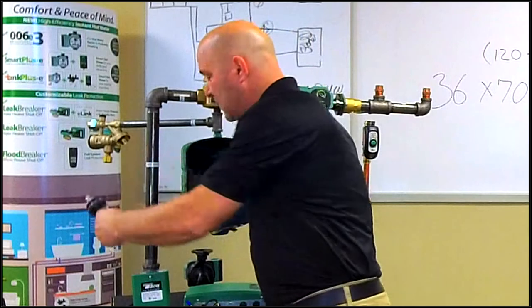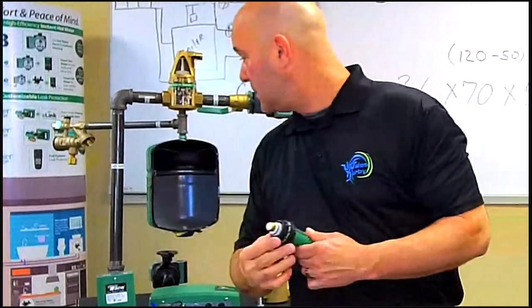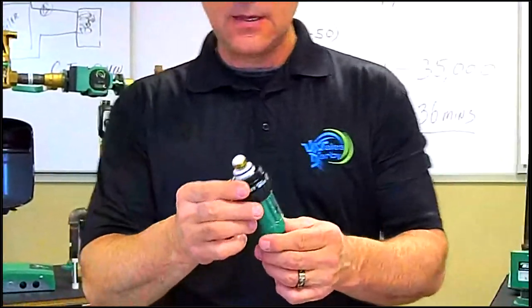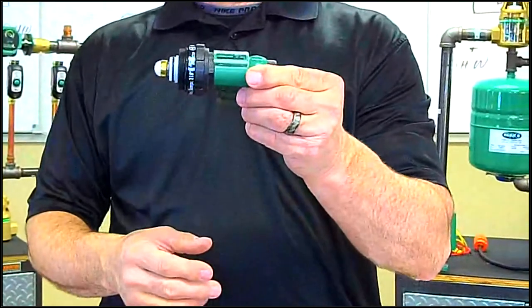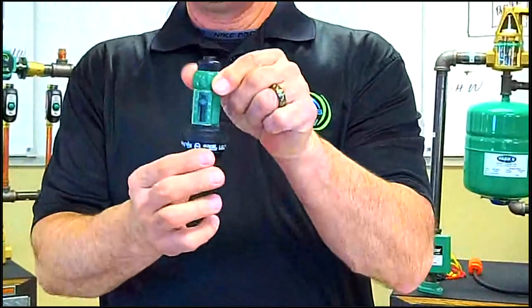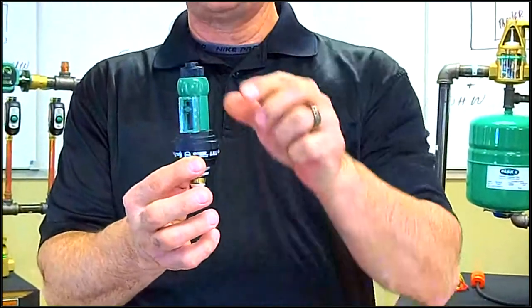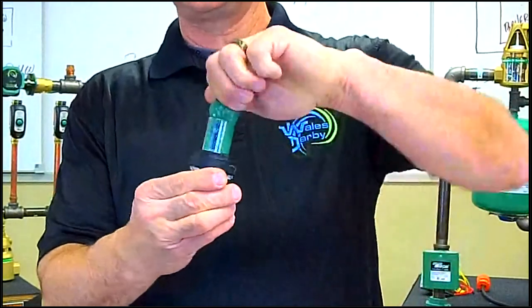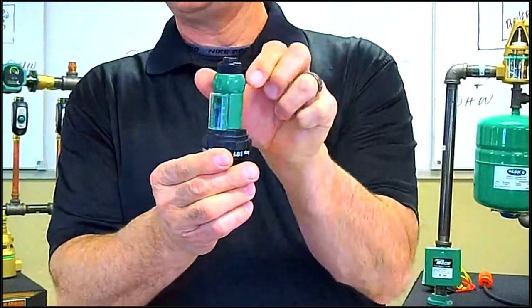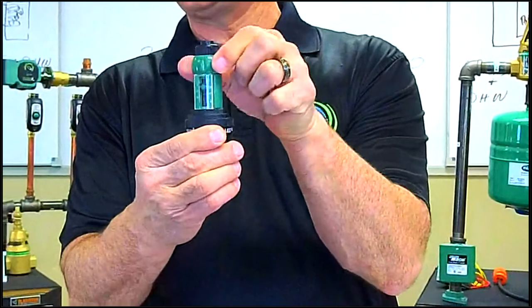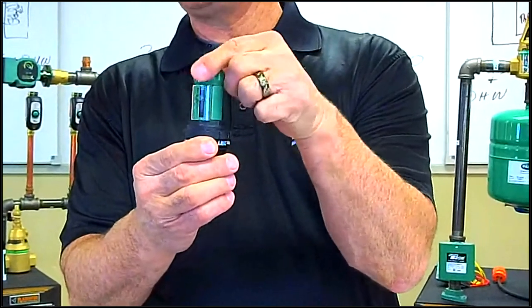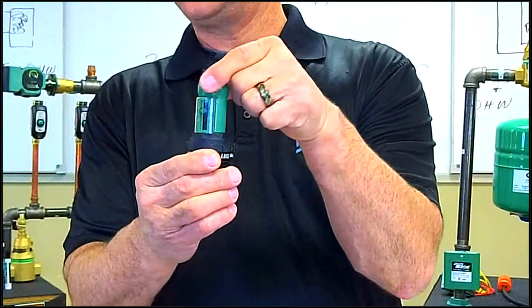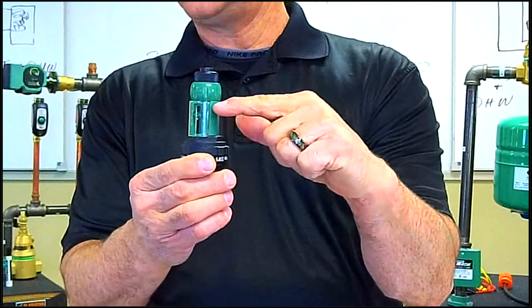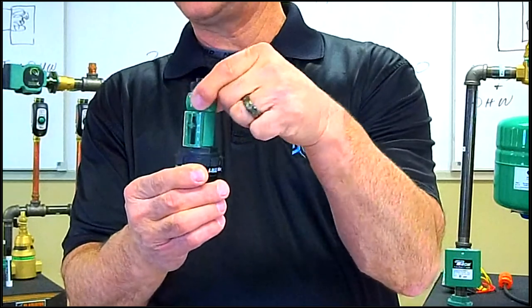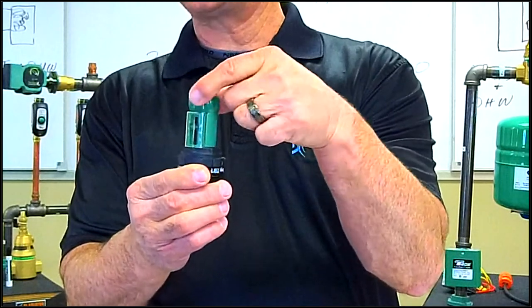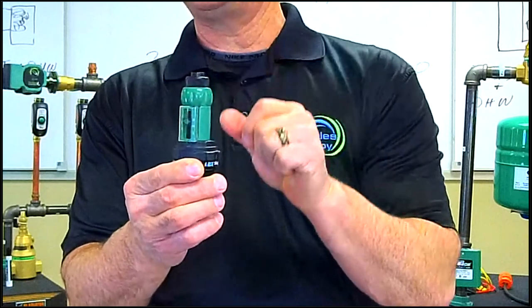So you have the ability here, this is a 3450. You have the ability to change out the components. So this feed valve, this is the feed valve side. You would just loosen up this little black knob right here and then take this green knob and you can rotate this. And you can see, hopefully you can see on the screen, that the little identifier inside here, the little green identifier is moving. That's adjusting the pressure in that system.